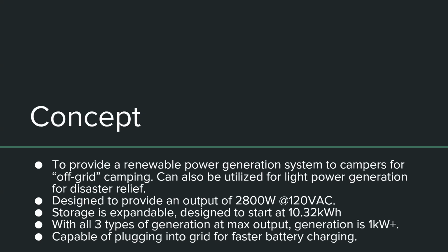So this particular system that we're looking at is designed to provide an output of 2,800 watts at 120 volts AC. The storage is expandable. It's designed to start at 10.32 kilowatt hours, but that is, like I said, easily expandable by putting additional batteries in parallel, as long as the batteries run on the same 12 volt bus that the system's designed for. And there's also other buses you can use, but we'll get to that later.